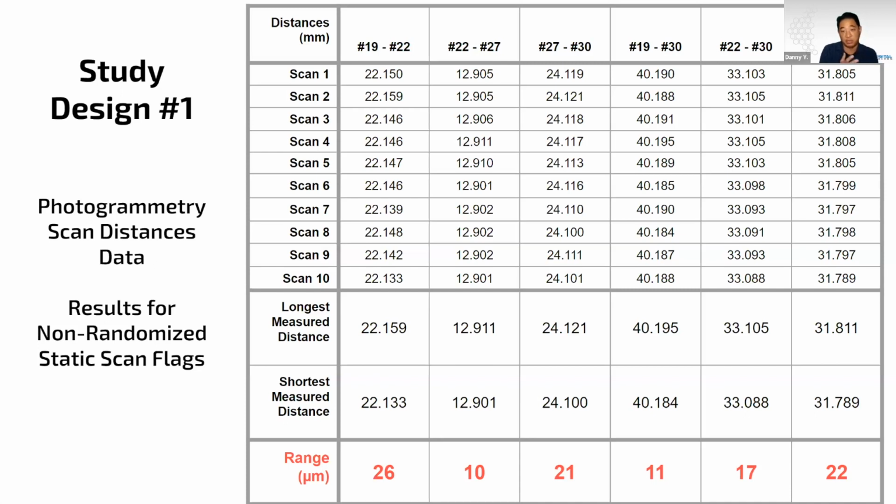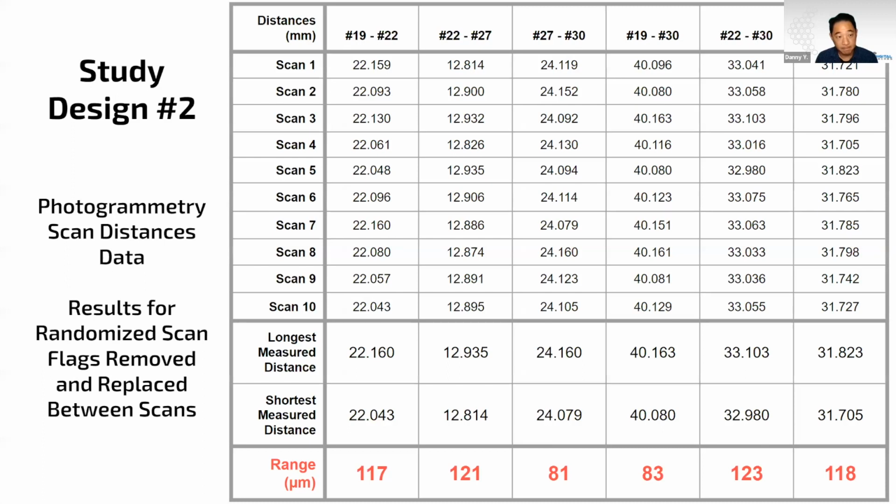So this is the variance between the 10 scans from each other, right? The 10 scans and the distances between the implant positions. You would basically have to cut this number in half. We're really close to that single micron accuracy when you're scanning it directly 10 times. These photogrammetry machines, when they're using new scan bodies, really are incredibly accurate. Now, when you actually go to a randomized model and you add that scan body accuracy and manufacturing accuracy into it, that changes the story significantly.